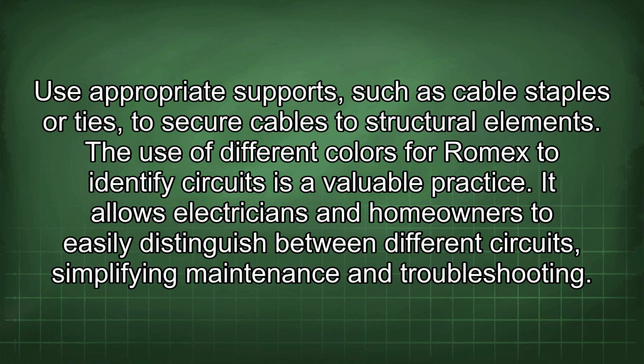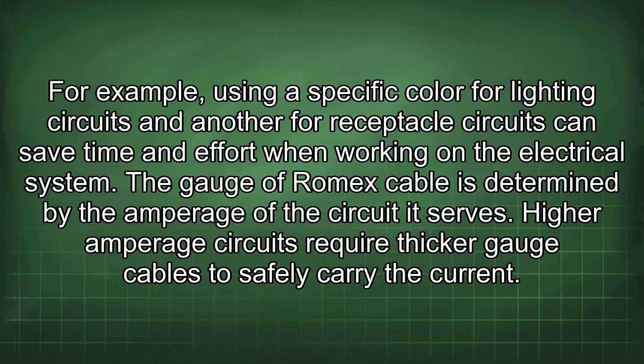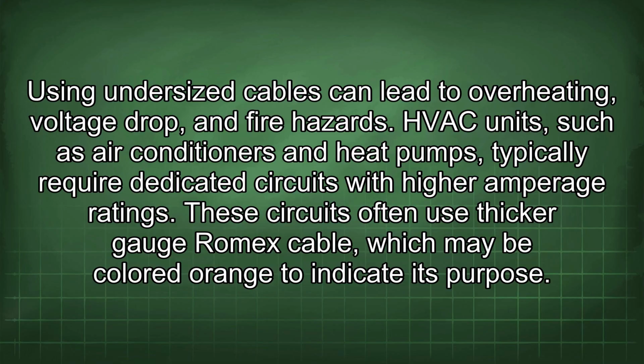The use of different colors for Romex to identify circuits is a valuable practice. It allows electricians and homeowners to easily distinguish between different circuits, simplifying maintenance and troubleshooting. For example, using a specific color for lighting circuits and another for receptacle circuits can save time and effort when working on the electrical system. The gauge of Romex cable is determined by the amperage of the circuit it serves. Higher amperage circuits require thicker gauge cables to safely carry the current. Using undersized cables can lead to overheating, voltage drop, and fire hazards.